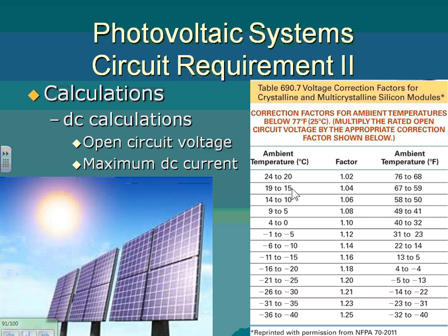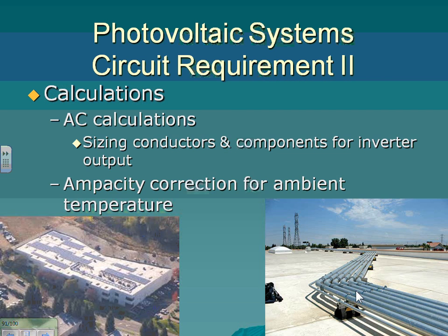Let me show you, this applies to us in Minnesota. The lower the temperature, the more voltage the modules can give you. For you guys, wherever you are, it's probably not a big deal, but for Minnesota it can go very low. Look at this multiplier: if the voltage is 100 volts, your module will provide 121 volts. Who cares? At a lower temperature, you might exceed the rating of your conductor. So that's how you adjust. I'm sure you pay a lot of attention to adjusting your voltage based on temperature, especially in a low temperature climate like ours. So that's a temperature calculation.